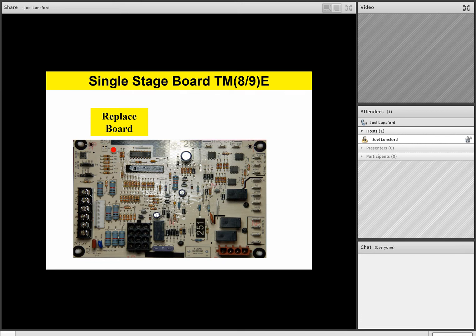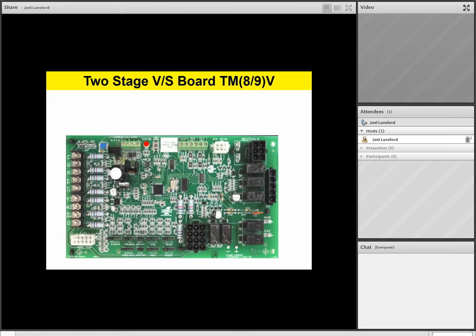Okay, let's take a look at another one. Here we have a green board, so we automatically know it's a two-stage board. Please refer to page number 22 in your handout or workbook for some two-stage board diagnostics. So we see we have a red LED and it has 13 red flashes. As you take a look in your workbook, page number 22, we have 13 red flashes on this two-stage board. As we dig a little bit deeper, these are some of the things we need to check. We have 13 red flashes. We need to check the following.